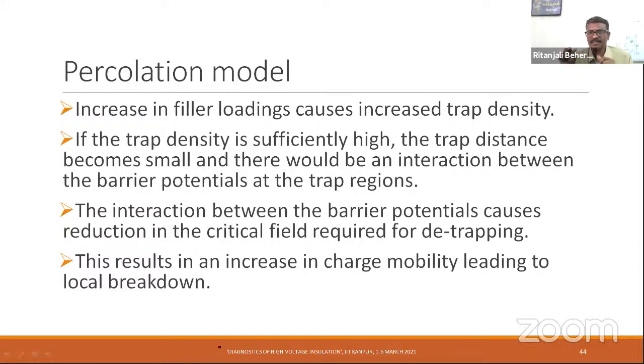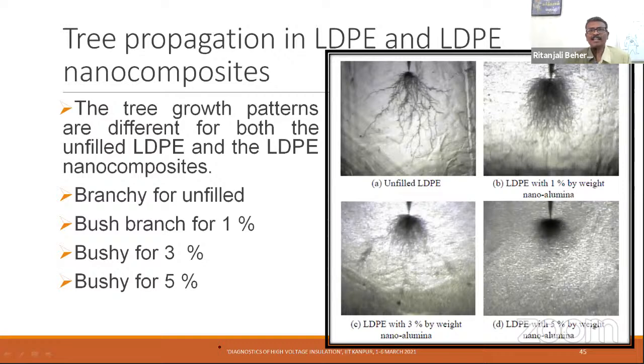This would enhance the field there, and the interaction between the barrier potential causes reduction in the critical field required for detrapping. There is a critical field at which the charges which got trapped at the filler will get detrapped. If they get detrapped, they will try to move forward along the direction of the field, though slow. So this results in an increase in the charge mobility in the polymer bulk, which leads to a local breakdown. That would be what might be taking place at the higher filler loading, and hence not only is the tree initiation quicker, but the breakdown is also quicker at a higher percentage of fillers. The tree propagation in LDPE and LDPE nanocomposites are observed here.